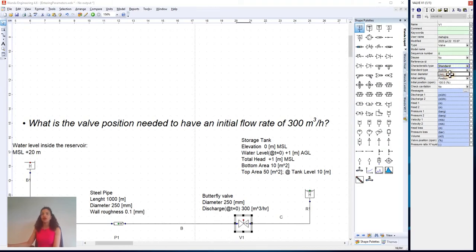We move on and fill in an inner diameter of 250 millimeters. Instead of having the position as the initial setting of the valve, we choose discharge, because we want to ensure an initial discharge through the valve of 300 cubic meters per hour.